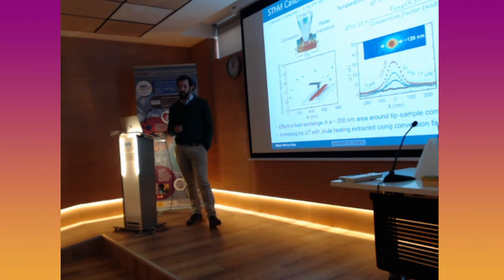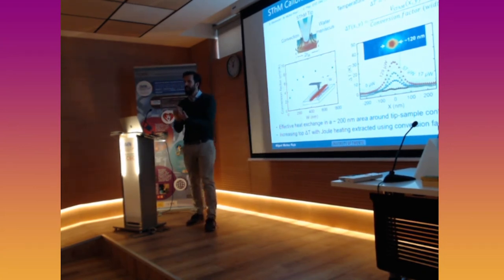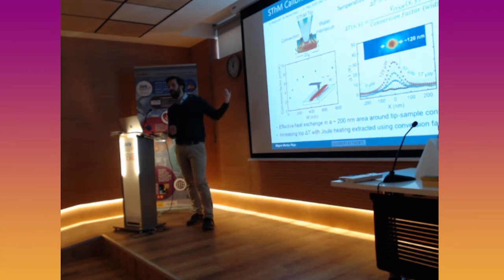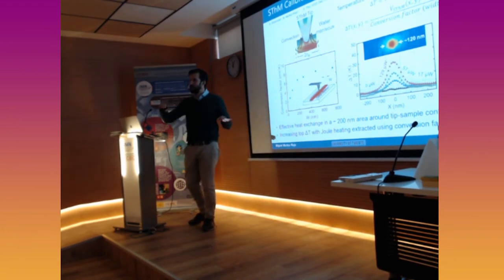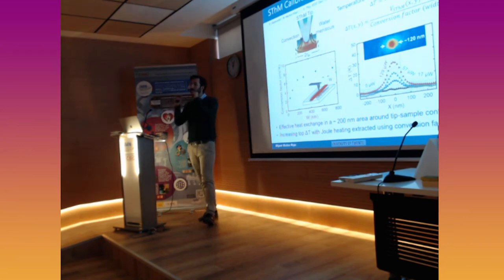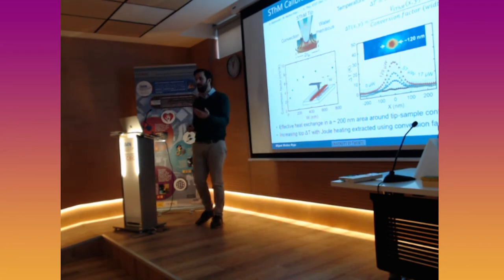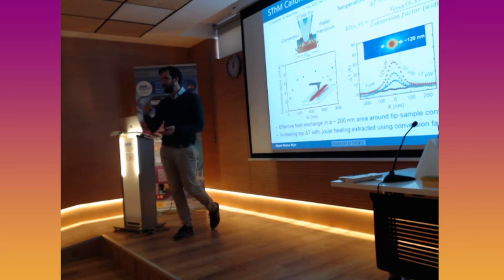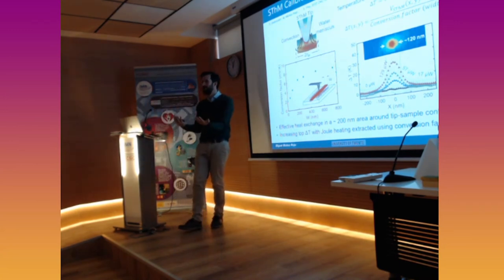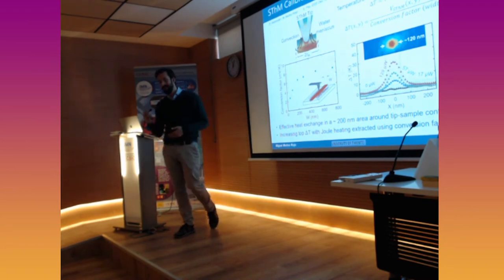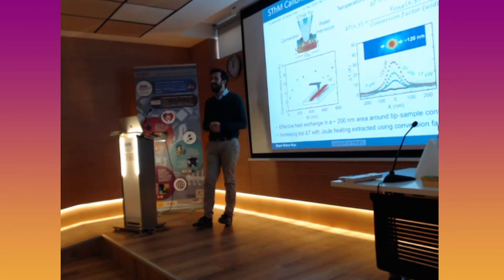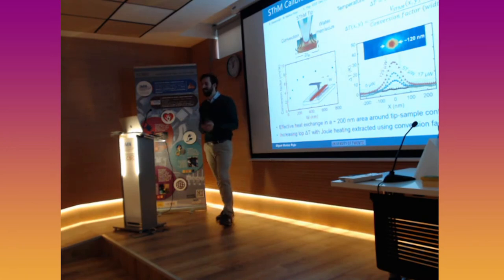Yes, that's actually very tricky, because that causes different types of thermal drift and changes the type of interaction between the probe and the sample surface. That's why we were also trying to calibrate at different temperatures with these kinds of lines, to see how to account for these parameters. Parameters like the pressure between the probe and the sample surface also affect it. This is one of the nightmares of this technique—but if it were easy, it would have already been done.